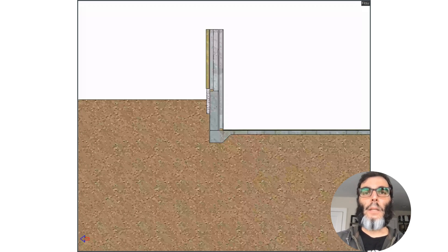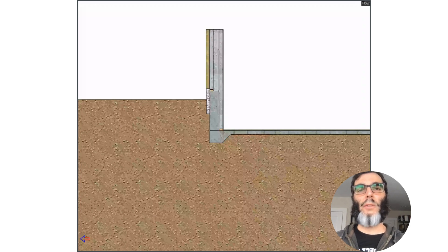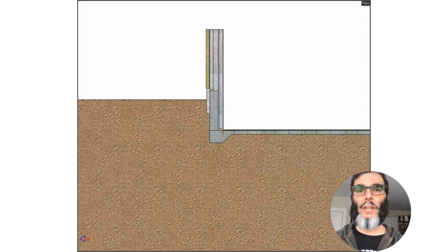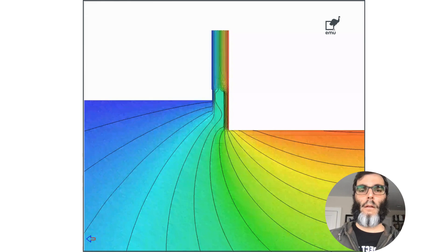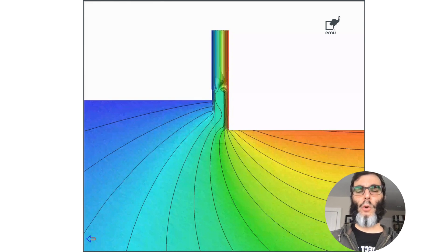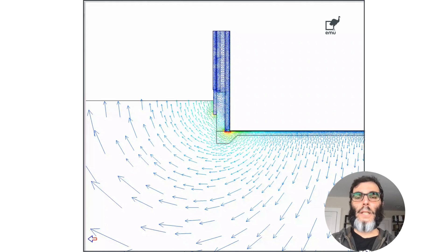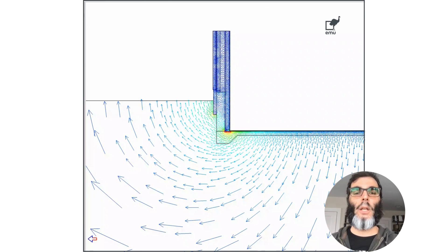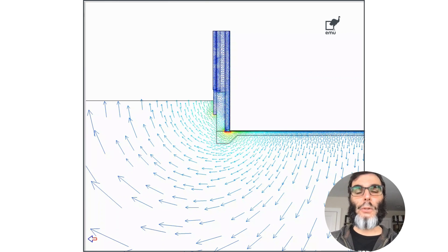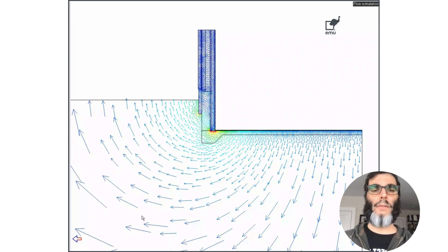Let's take a look at the detail we received from the architects before we start proposing changes and see how things can be done better. Here we have the isotherm view of this junction — the peacock tail image we started the video with. As we look at the direction of the heat flow and its intensity, we see there's a lot of heat flow going out, not just from the slab edge, but also from the center of the slab, all the way down into the dirt to the outside air.